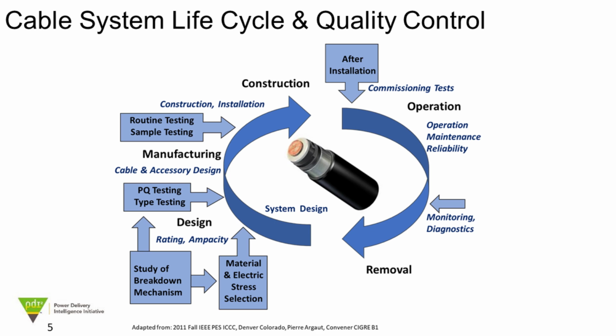Well, the reality is, as Sharif said, every joint or termination or cable reel is tested in the factory using an overvoltage and a partial discharge test. And as best practice, and we're going to be talking more about this later in this presentation, but I'll mention it now, if we can repeat that test in the field, we can also do a power frequency or near power frequency partial discharge test in the field and get a comparative baseline.